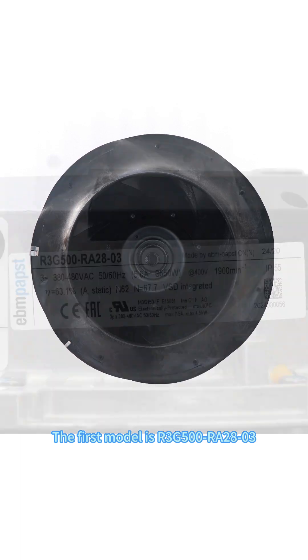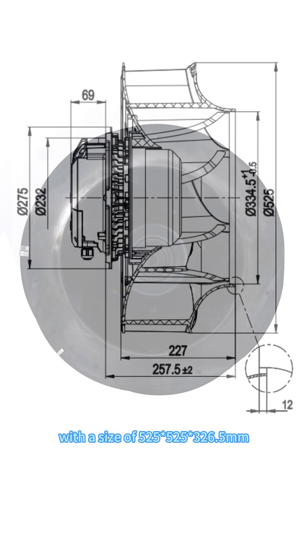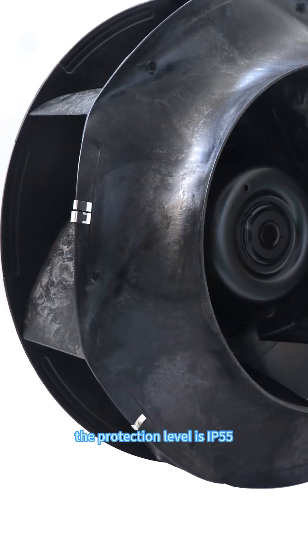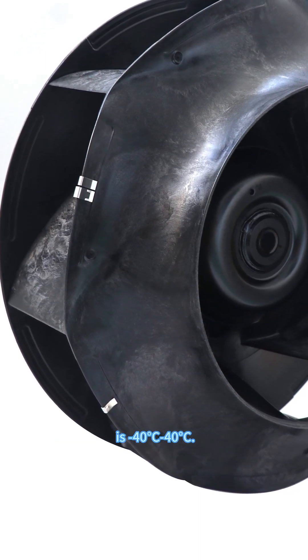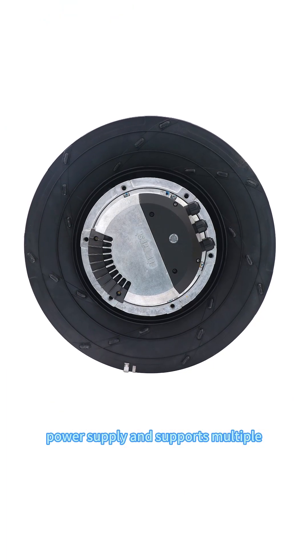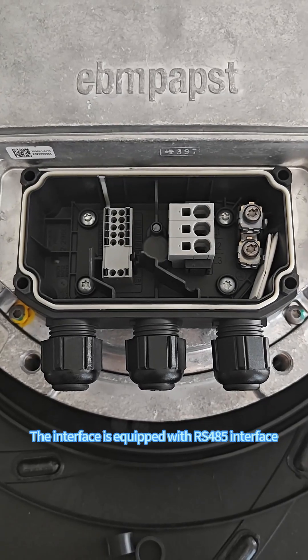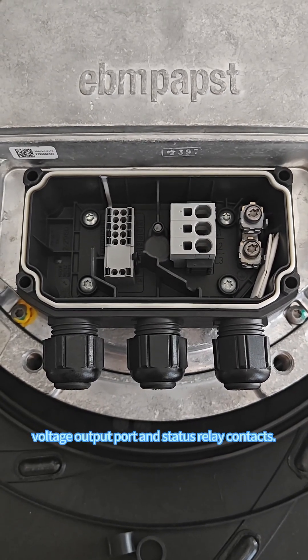The first model is R3G500-RA28-03, an EC backward centrifugal fan with a size of 525 by 525 by 326.5 millimeter. The material of the impeller is PP plastic, the protection level is IP55, and the operating temperature is between minus 40 degrees and 40 degrees Celsius. The fan is powered by a three-phase power supply and supports multiple speed regulation methods and Modbus protocol. The interface is equipped with RS-485 interface, multifunction IO port, voltage output port, and status relay contacts.